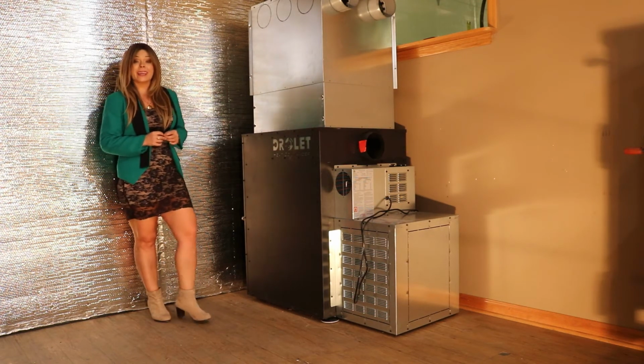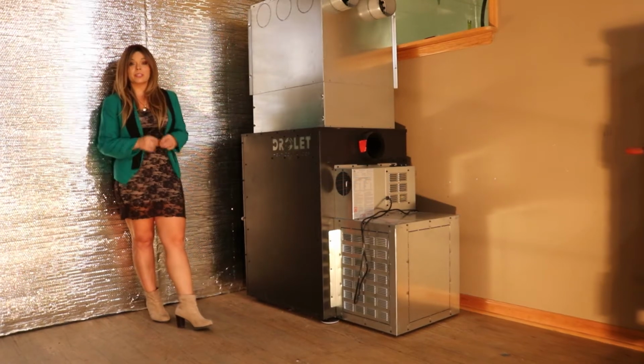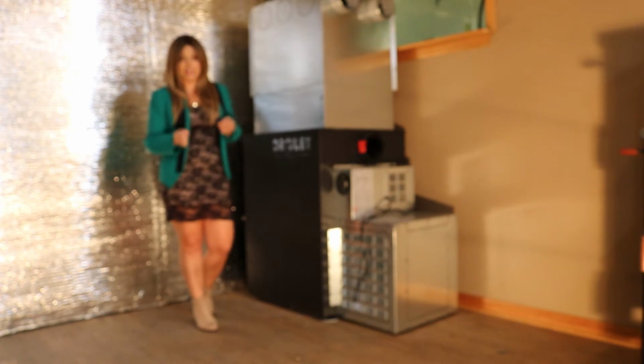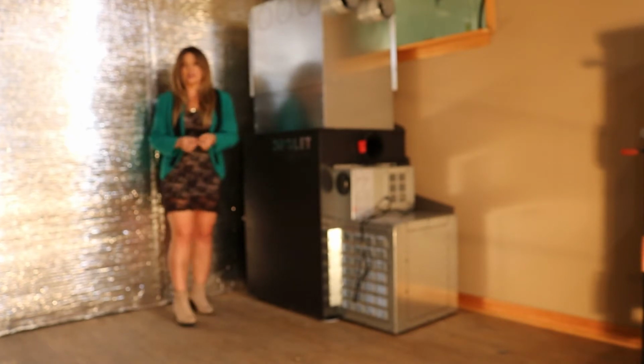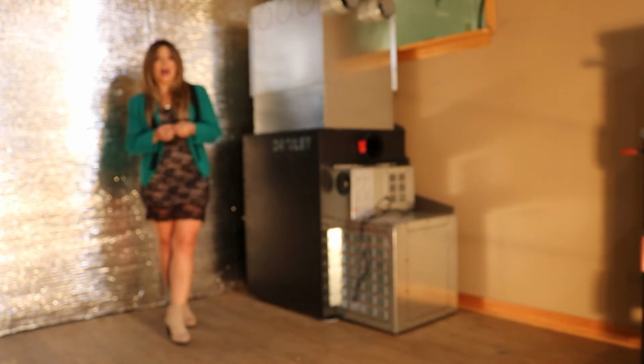The Drolet Heat Commander EPA wood furnace. Today we're going to talk about what is going on if you have a fast green blinking light on the front of your furnace. Essentially what this means is that the unit is getting too hot, the firebox is getting too hot, but the blower is not kicking on to essentially move that air. This is a problem because you are now essentially at risk of overfiring and overheating your furnace, which you don't want to do. There are a couple reasons that it could happen that the blower is not kicking on.